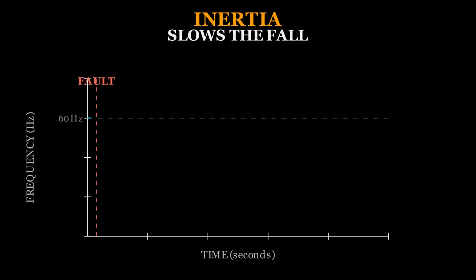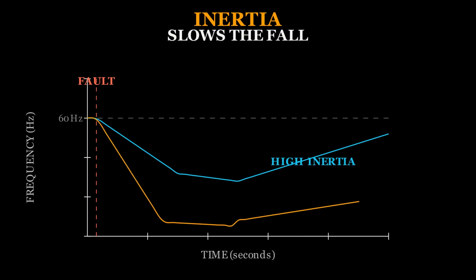The rate at which frequency changes after a disturbance is called ROCOF, rate of change of frequency. In a high inertia system, ROCOF might be negative 0.1 Hz per second after a large generation trip. In a low inertia system, the same event produces negative 0.5 Hz per second or worse. That difference doesn't sound like much. In practice, it's the difference between a controlled response and a cascade.